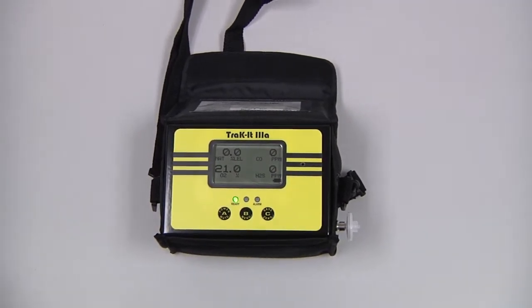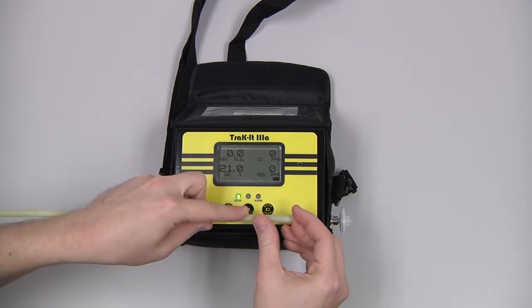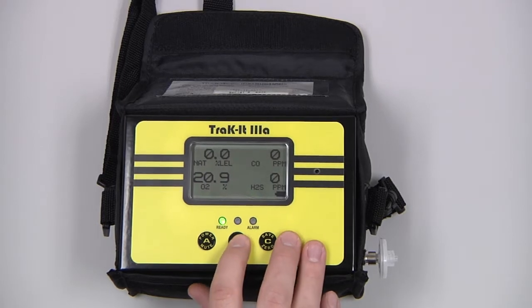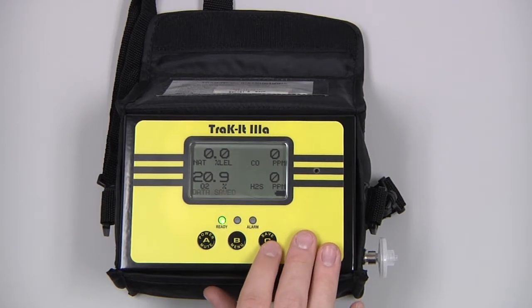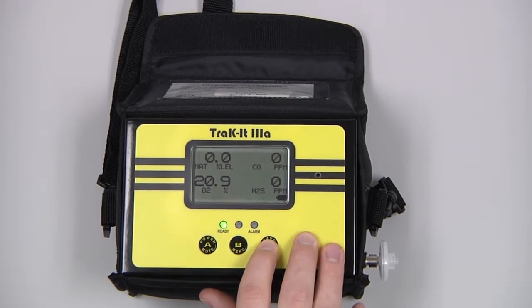If you're using an attachment such as a bar hole probe, we would need to do the same thing by attaching the probe and blocking the inlets until we get a flow blocked indication. During use, pressing and releasing the A button will mute an alarm. Pressing and releasing the B button will access the quick menu. Pressing and releasing the C button will save the data on the screen. Pressing and holding the C button in a cleaner environment will auto-zero the instrument.